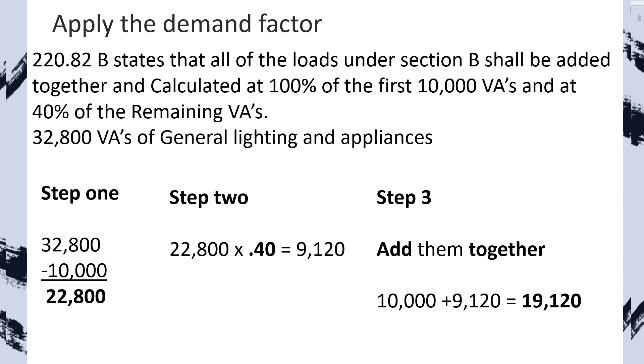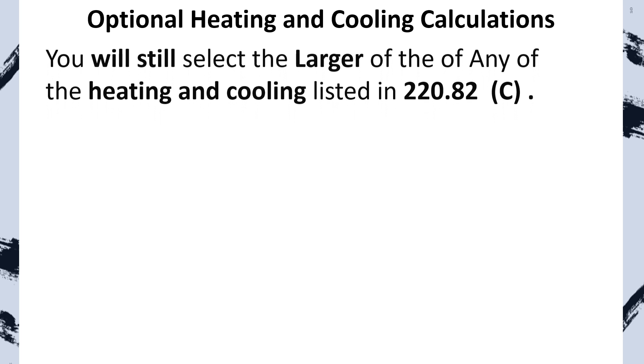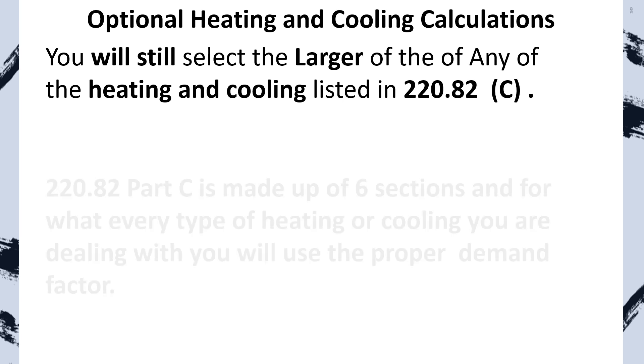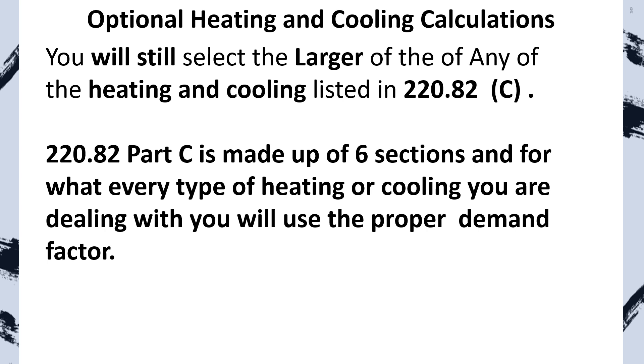For heating and cooling with the optional method, we still choose the larger of the two. These rules are laid out in 220.82(C) — there are six different parts and each one tells you exactly what to do. It's straightforward: once you've calculated the heating and the cooling, you simply select the larger of the two and add it to your reduced load to get your whole home load calculation.